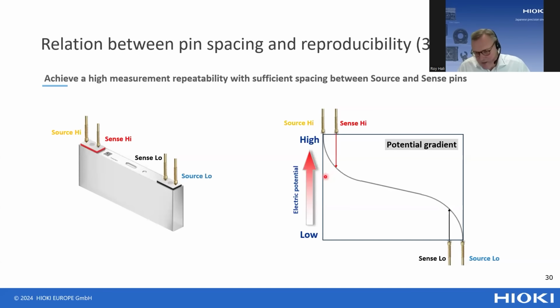At the production line, reproducibility is normally considered more important than absolute accuracy, because you want to be able to compare the test results from day 1 with the ones from day 3 or from day 10. Positioning the source and sense probes a little bit further apart will help you to achieve a better reproducibility of your measurement.